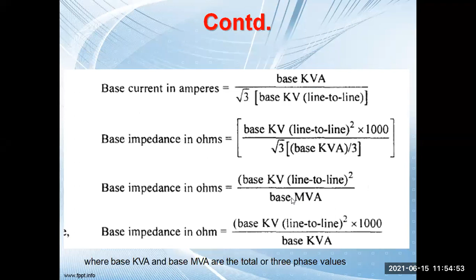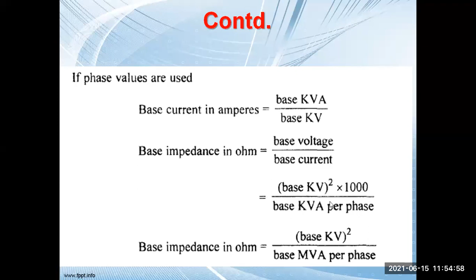Is it clear, these formulas? Okay. So in all the above relations, the power factor is assumed to be unity. Whatever calculation we are doing, we are assuming that the power factor of this system is unity. So base power in kilowatt is equal to base kVA. So how to calculate the per unit impedance? It is the actual impedance in ohms into base kVA by base kV square into 1000. So it is basically actual impedance by the base impedance. You have already calculated the base impedance, base kV square into 1000 by base kVA. So you have just substituted this.